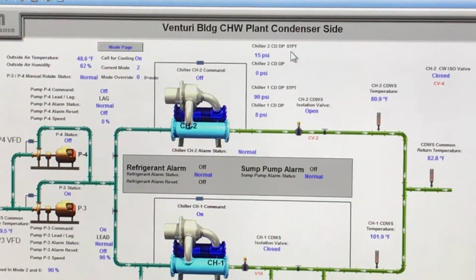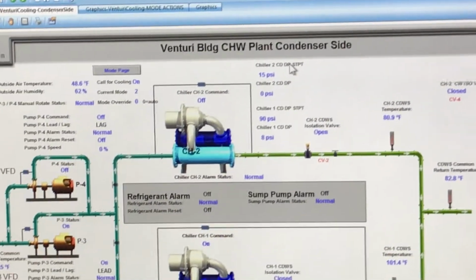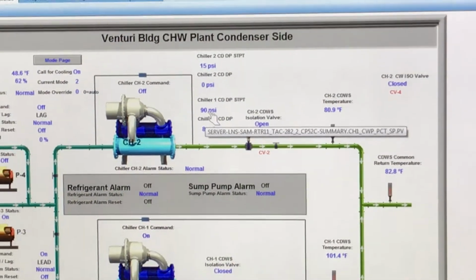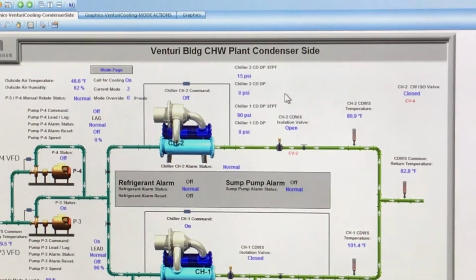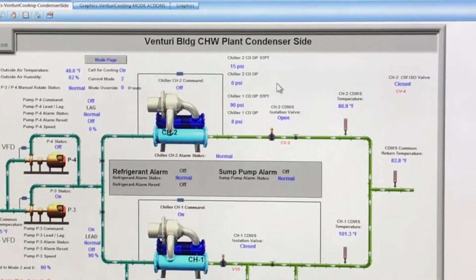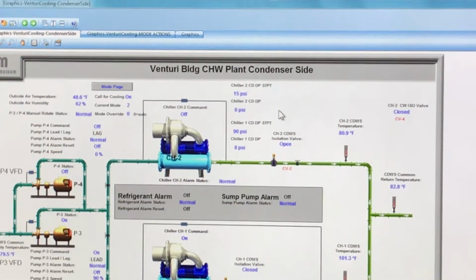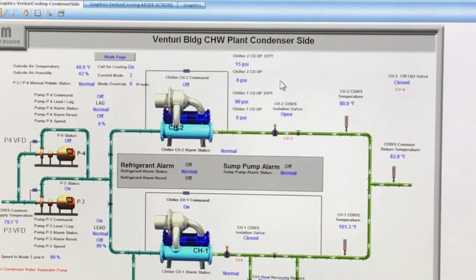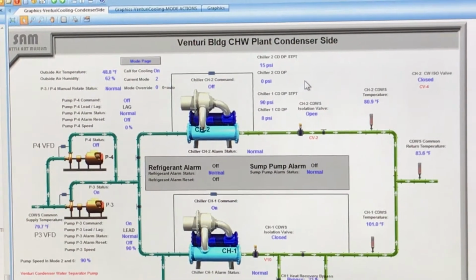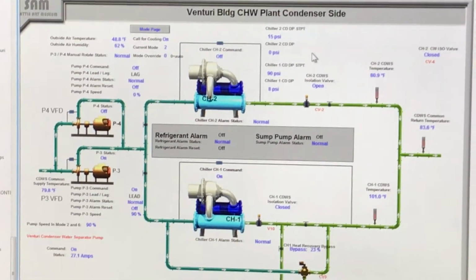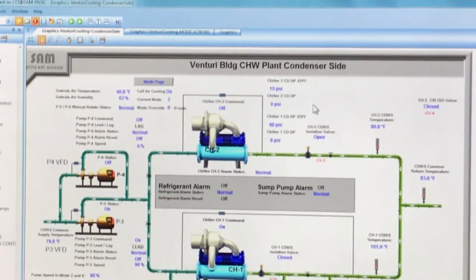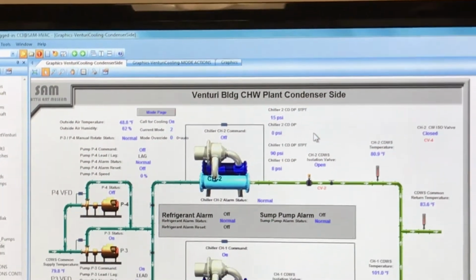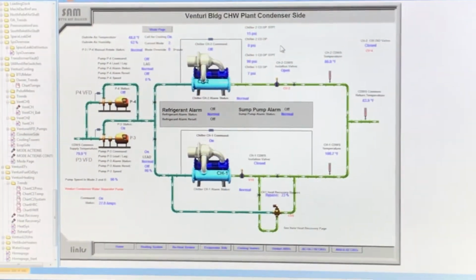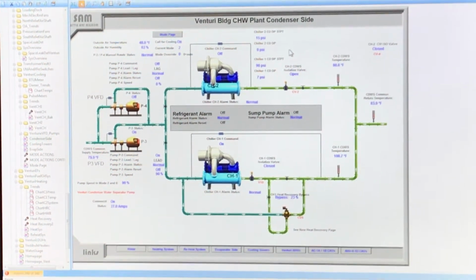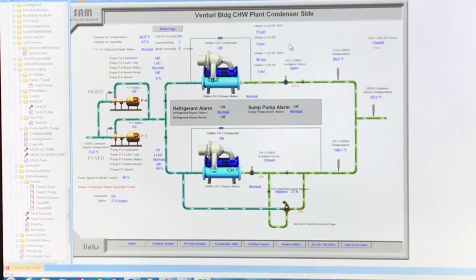Yeah, maybe we could get Sam to explain this one. The differential pressure set points. Notice that this differential set point is at 90. Is that erroneous? For one thing, there is a slight glitch in this graphic because the heat exchanger is not there. And the other thing is, when you are running chiller 1, the cooling tower is actually going through the heat exchanger. So your set point is not really very critical as long as you have the minimum flow or design flow through the condenser.